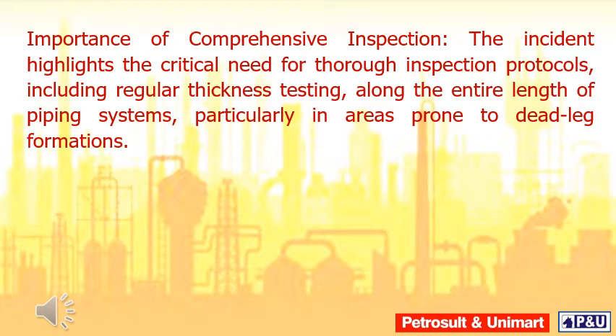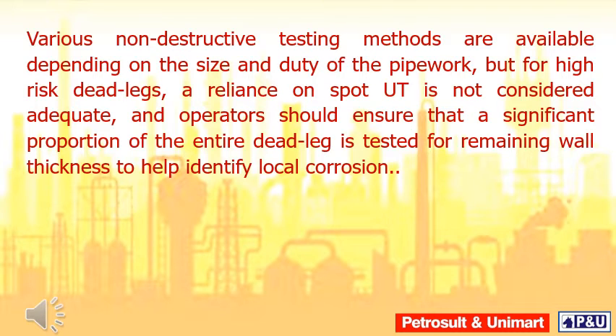The incident highlights the critical need for thorough inspection protocols, including regular thickness testing along the entire length of piping systems, particularly in areas prone to dead leg formations. Various non-destructive testing methods are available depending on the size and duty of the pipework, but for high-risk dead legs, a reliance on spot UT is not considered adequate. Operators should ensure that a significant proportion of the entire dead leg is tested for remaining wall thickness to help identify local corrosion.